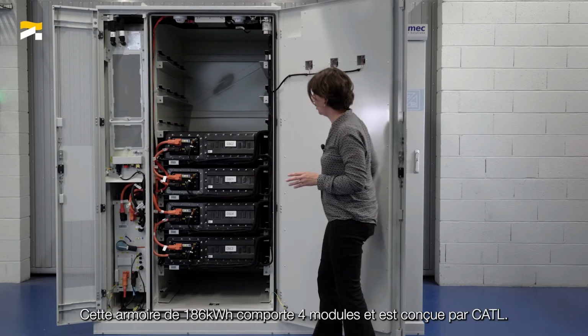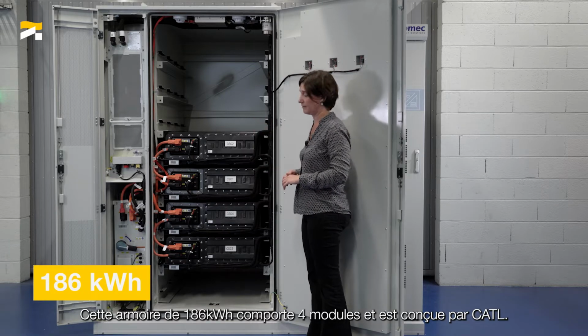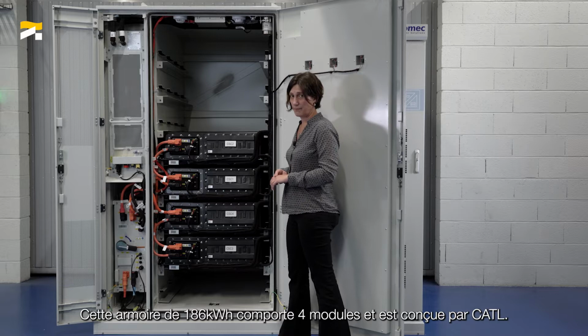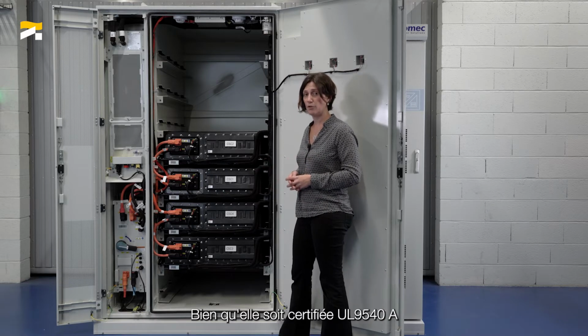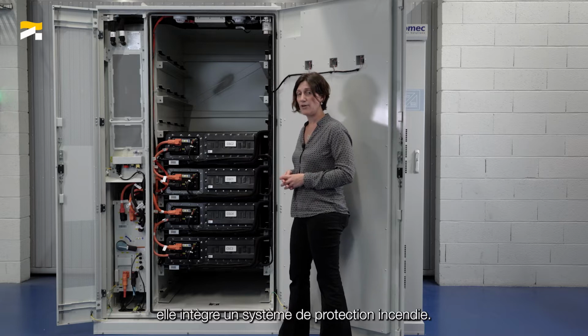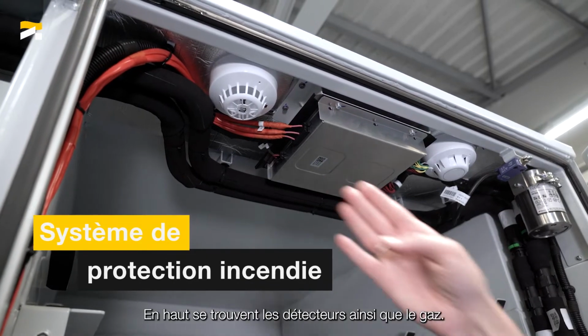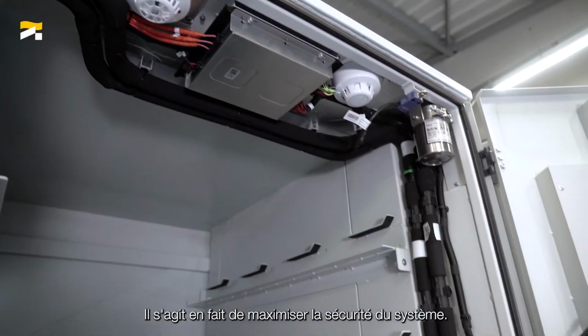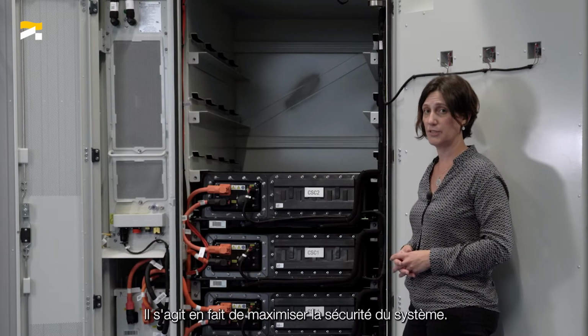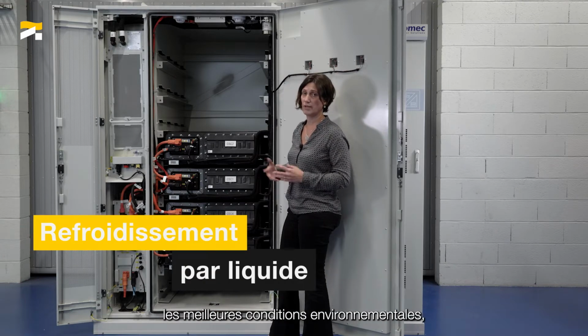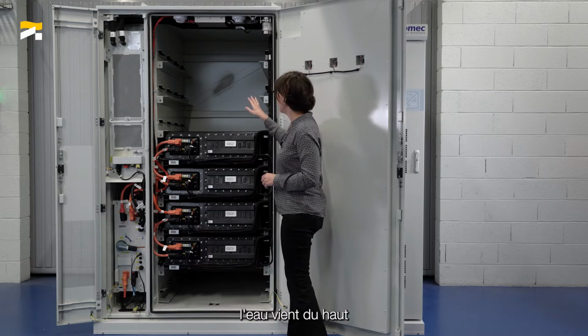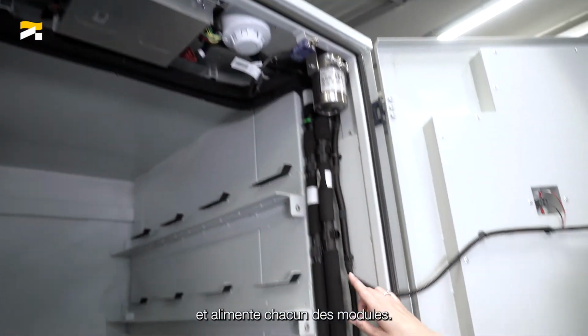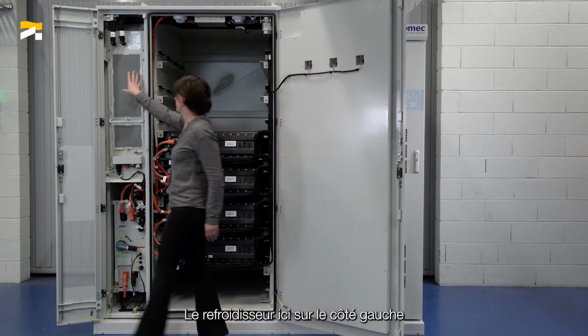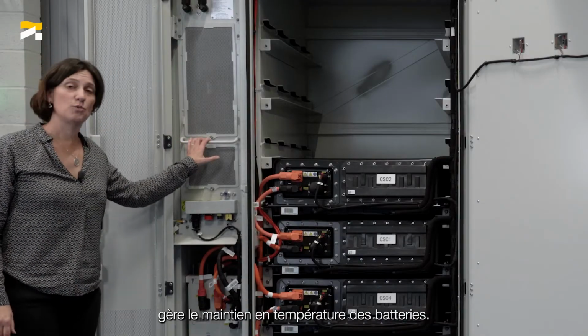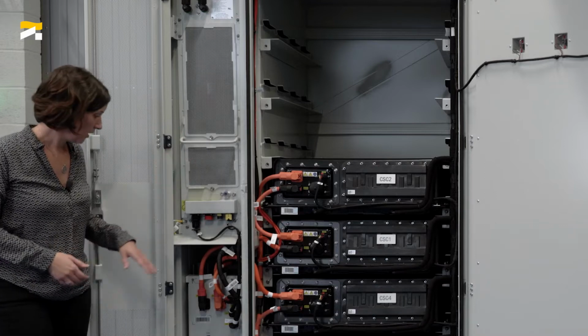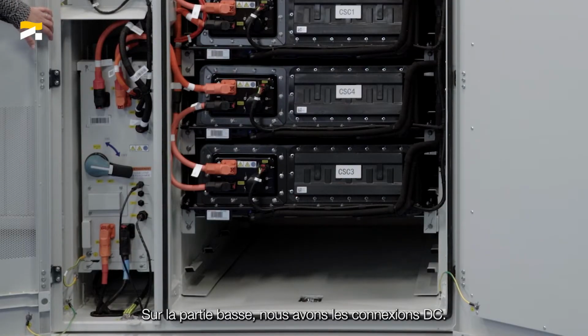This is a 4-module 186 kWh cabinet designed by CATL. Though it has been UL 9540A certified, it still has a fire system integrated. On the top we can see the detectors and the gas. This is really to maximize the system safety. The system is also water-cooled to enable better environmental conditions, and the water comes from the top and goes to each of the modules. The chiller is here on the left side, and it manages the warming and the cooling of the battery. On the bottom part we have all the DC connections.